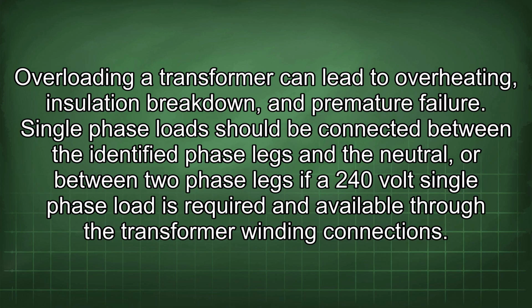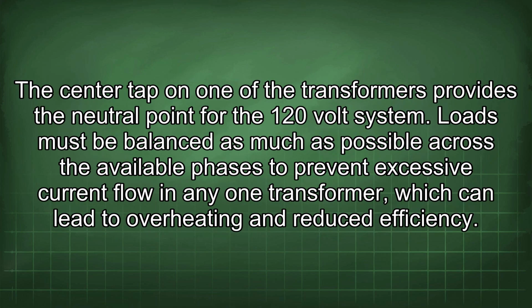Single-phase load should be connected between the identified phase legs and the neutral, or between two phase legs if a 240 volt single-phase load is required and available through the transformer winding connections. The center tap on one of the transformers provides the neutral point for the 120 volt system. Loads must be balanced as much as possible across the available phases to prevent excessive current flow in any one transformer, which can lead to overheating and reduced efficiency.